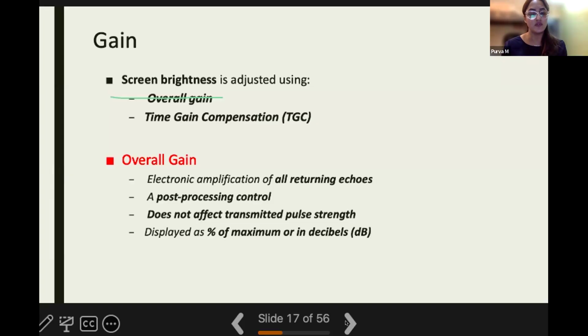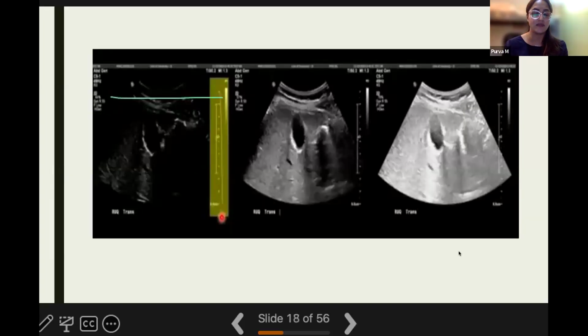In case we do increase the overall gain, our image is going to look something like the image on the right. If you increase it too much, this is overgain. If you notice here, we've lost contrast and we have a very noisy image. While if you look to the left, we have a very undergained image because we cannot really look at the structures or discern the boundaries of any structure here. The image in the center shows optimal gain.